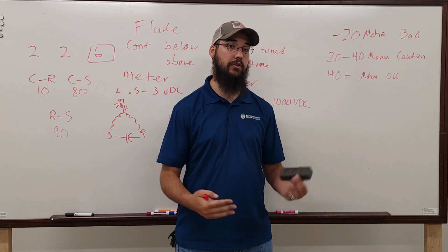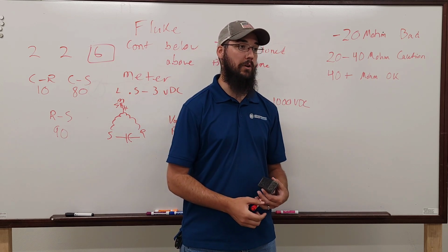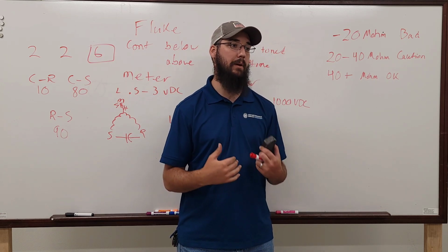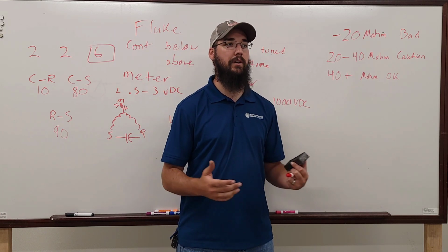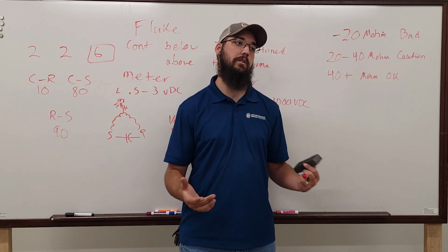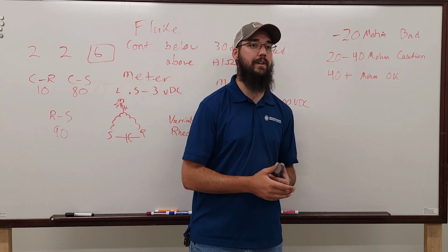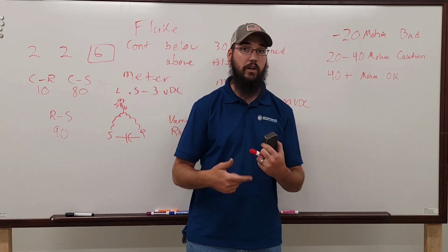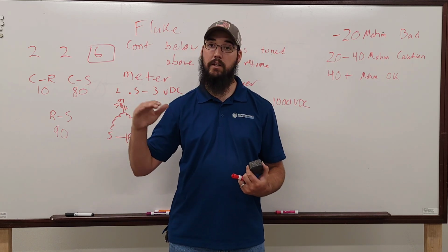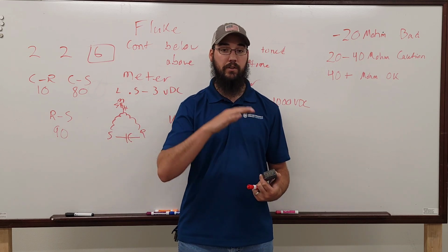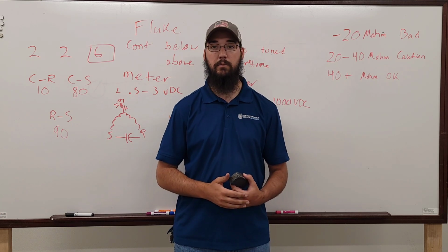If we were to take that much time, and it takes a lot of time to really analyze it and somebody paying attention to it, from a customer standpoint, theoretically, it's why we give them the reports, right? We're not technically paid to give them a full system analysis every time. We go in to do preventative maintenance to try to catch as much as we can that's in front of us. But if you wanted to start talking a real in-depth analysis, these are the readings you would be watching for every inspection. And you're looking for any deviation. And that deviation indicates to you, depending on the scale of it, all right, you've got about 6 months or you've got 5 years. Start budgeting now.